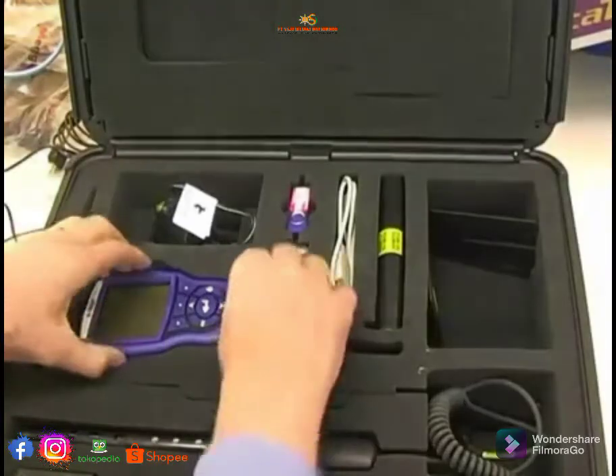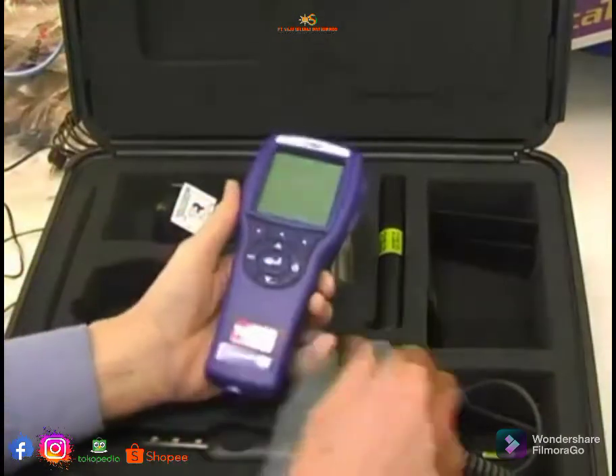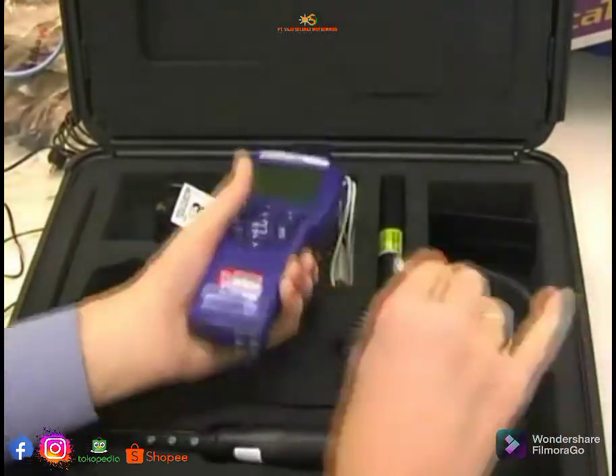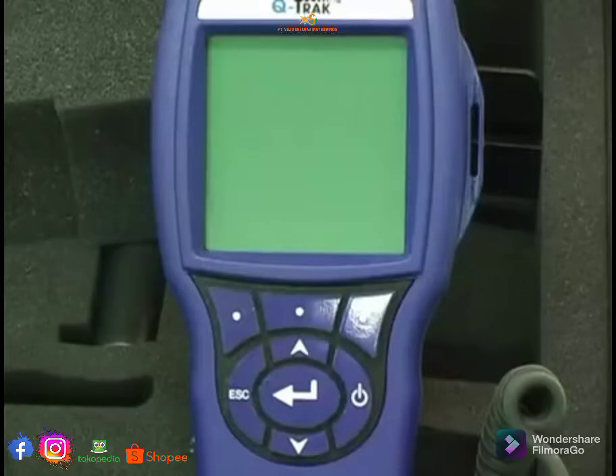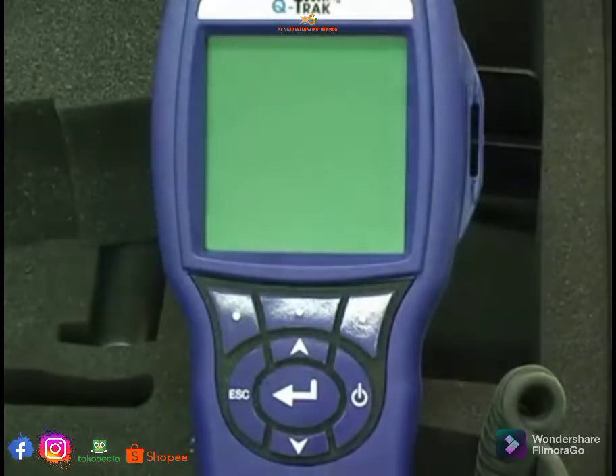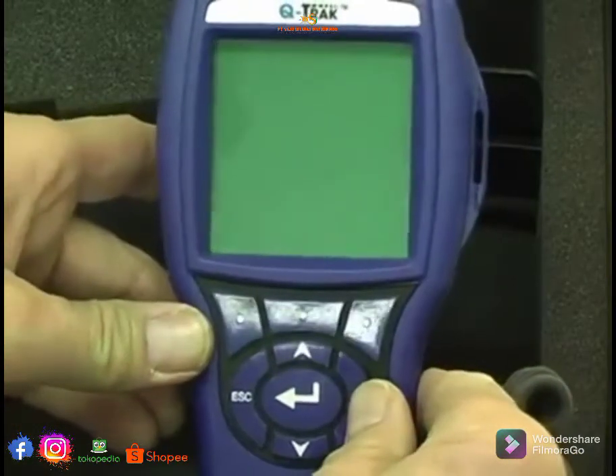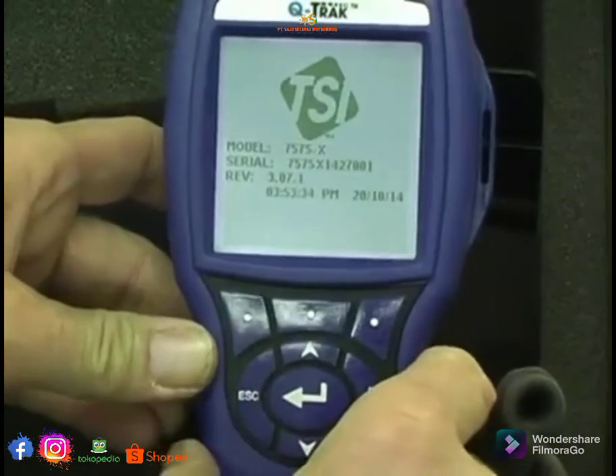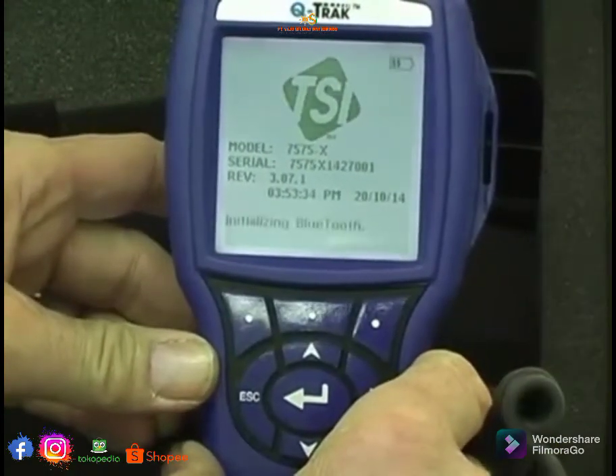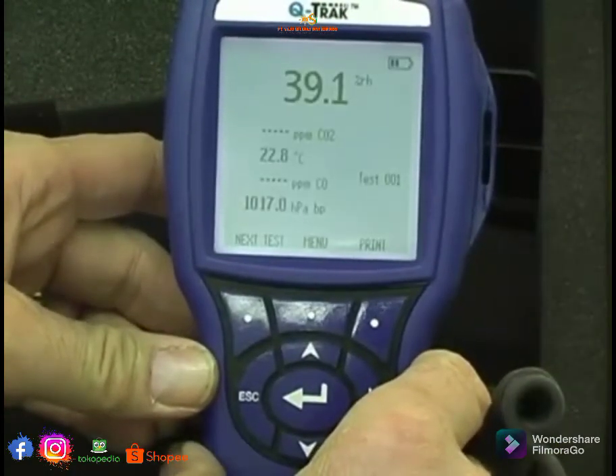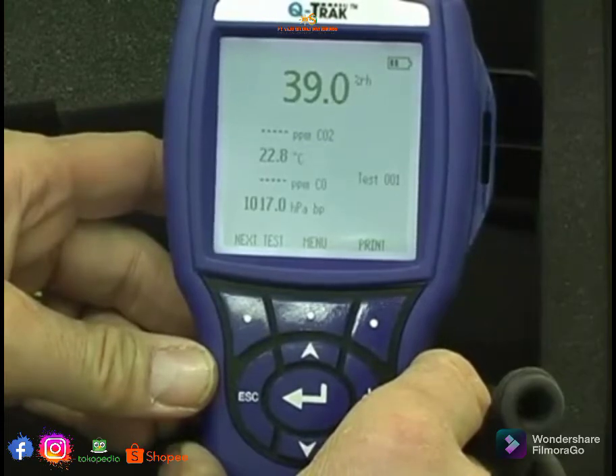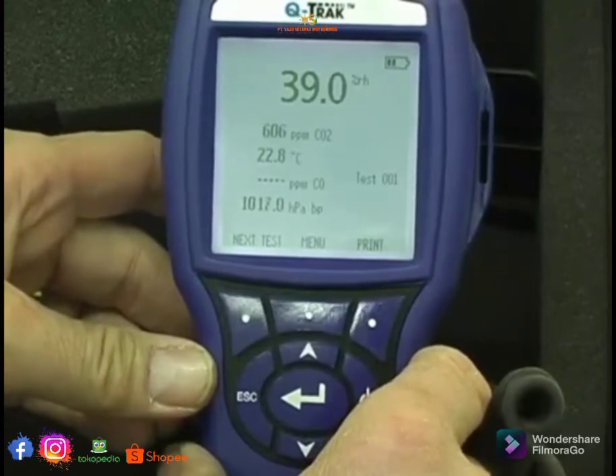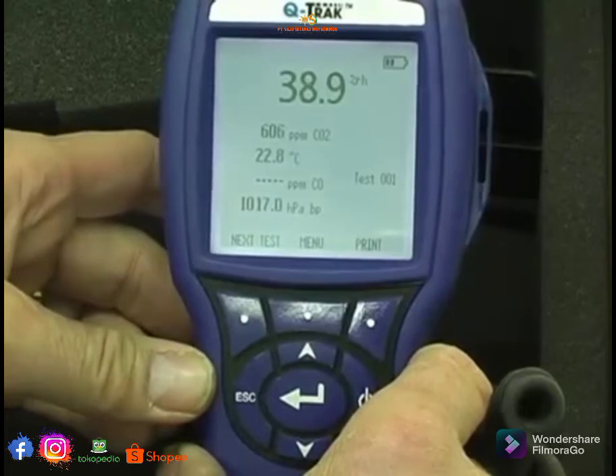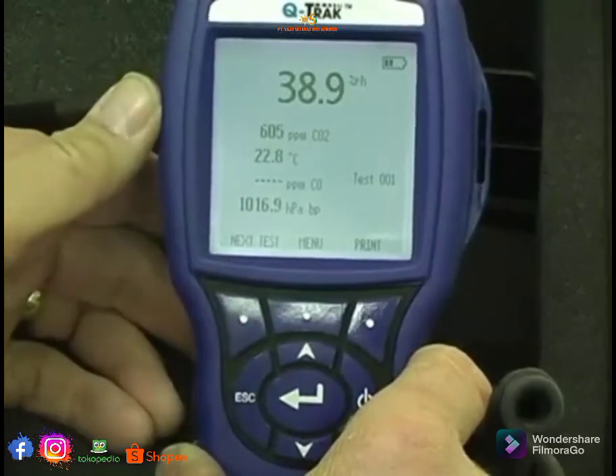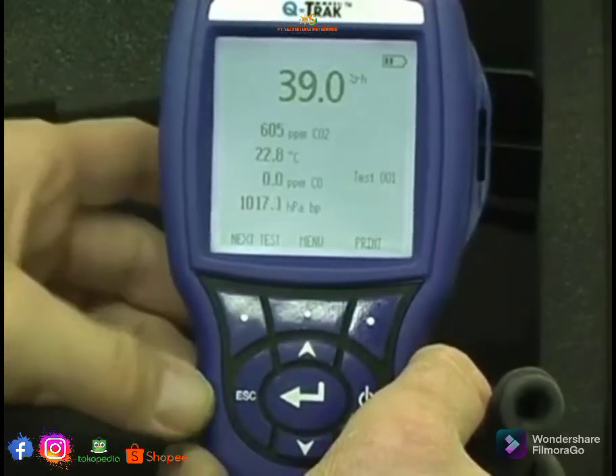Now to set the instrument up and get it going, it's simply a matter of taking the instrument. We've got to plug the probe in. Right, we turn this instrument on, we've connected the probe. Now this instrument will measure temperature, humidity (RH), also the barometric pressure, CO2 and carbon monoxide, CO. CO is useful for determining whether or not you've got problem issues with air from car parks, etc.